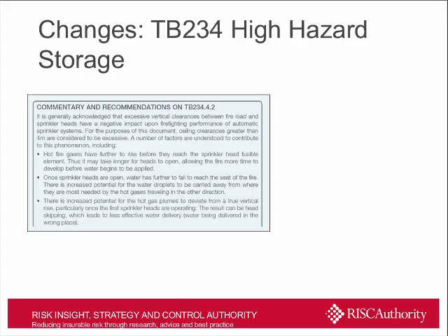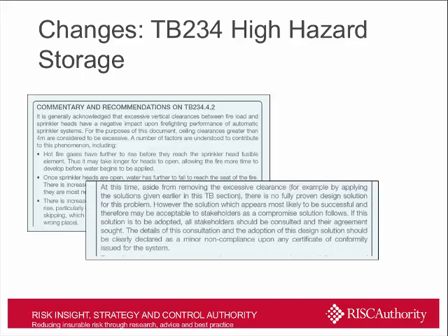So the sprinkler protection approach manages this issue fairly well by using relatively large droplets of water, which are less prone to drifting and disrupting the up-down communication, heat up, water down, that is critical to success. But nevertheless, there are limits to the vertical distance before performance is compromised.